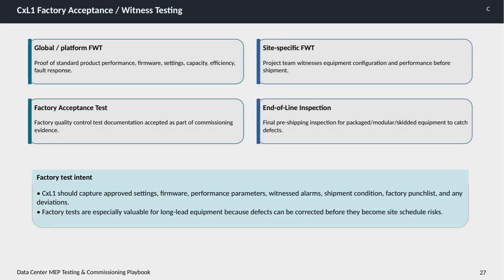On this slide, we're focusing on the CxL1 factory acceptance and witness testing process, which is a crucial part of the data center MEP testing and commissioning playbook. First, the global or platform factory witness testing serves to prove the product's standard performance. This includes verifying firmware, settings, capacity, efficiency, and fault response to ensure everything functions as expected.